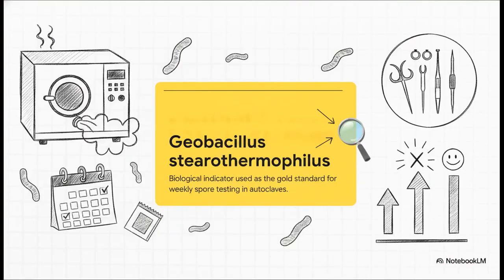Now, the autoclave is absolutely, hands down, the most important piece of equipment in any studio. It's the bedrock. If this machinery isn't functioning up to the absolute highest industry standards, none of that amazing art or high-end jewelry matters one bit. To prove an autoclave actually works, we use a biological indicator called Geobacillus stearothermophilus. That is the absolute gold standard for weekly spore testing. And the keyword there is weekly. If a studio is running these tests monthly or worse, only when the health inspector is due to show up, they're operating purely on trust. Why? Because a single undetected failure means every single instrument in that cycle, and potentially hundreds of clients processed afterward, was not sterile. Weekly validation catches those failures before they ever reach a client.